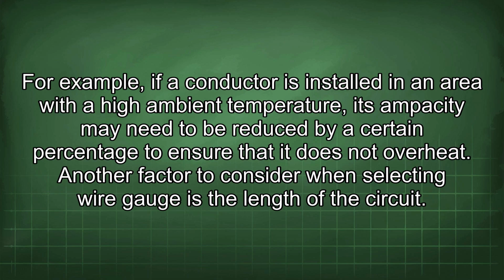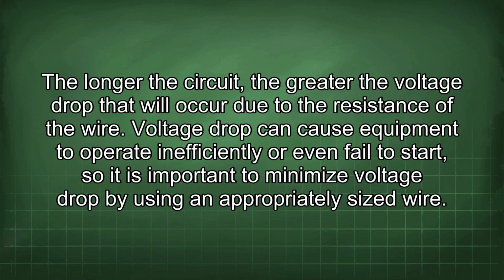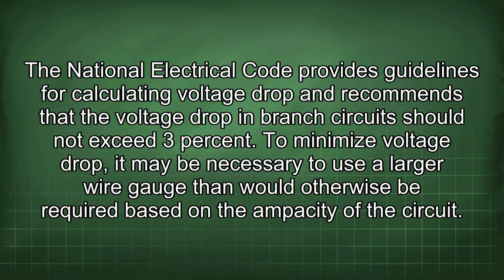Another factor to consider when selecting wire gauge is the length of the circuit. The longer the circuit, the greater the voltage drop that will occur due to the resistance of the wire. Voltage drop can cause equipment to operate inefficiently or even fail to start, so it is important to minimize voltage drop by using an appropriately sized wire. The National Electrical Code provides guidelines for calculating voltage drop and recommends that the voltage drop in branch circuits should not exceed 3%. To minimize voltage drop, it may be necessary to use a larger wire gauge than would otherwise be required based on the ampacity of the circuit.